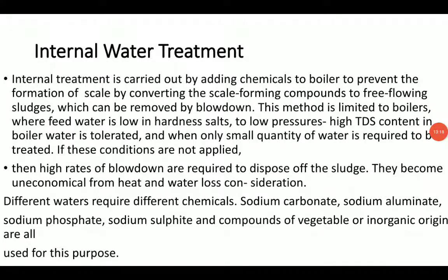Okay, so this method is limited to boilers where feed water is low in hardness salts. Low in hardness salts means we get fresh feed water which doesn't contain calcium carbonate, sodium carbonate, etc. At low pressure, high TDS content in boiler water is tolerated. Then high rates of blowdown are required to dispose of sludges. They become uneconomical from heat and water loss consideration.